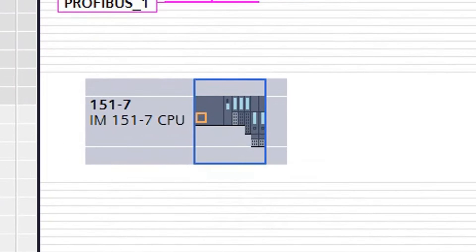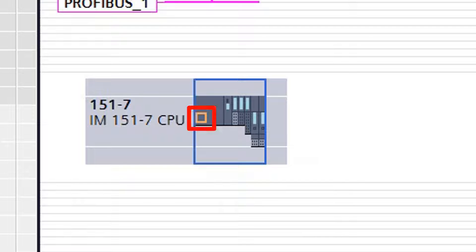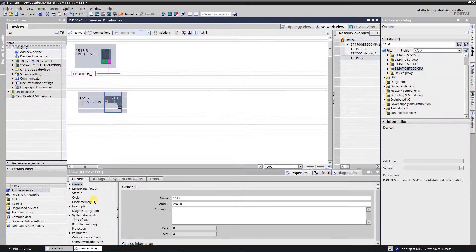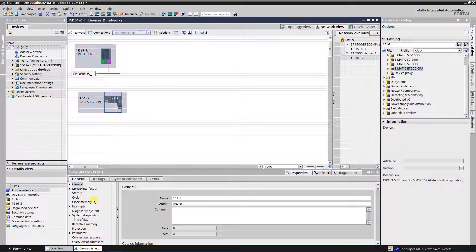If you take a closer look, you will see that IM151-7 does not have PROFIBUS interface. The orange color says that it is MPI interface. Well, you shouldn't worry about that, it is normal behavior, as by default, MPI interface is active on newly inserted module.